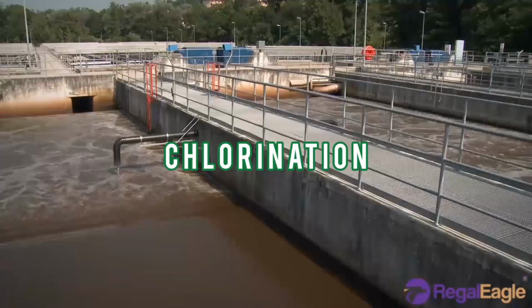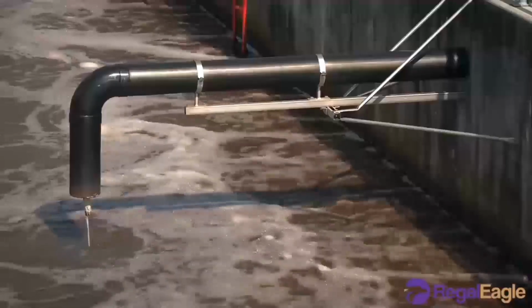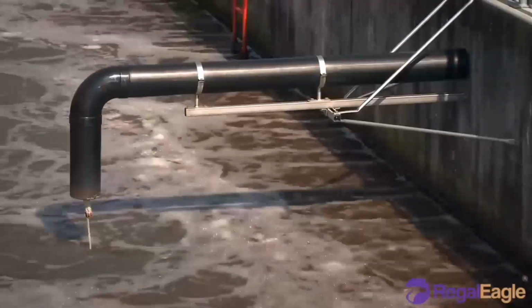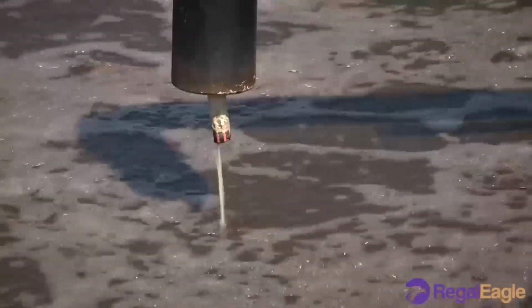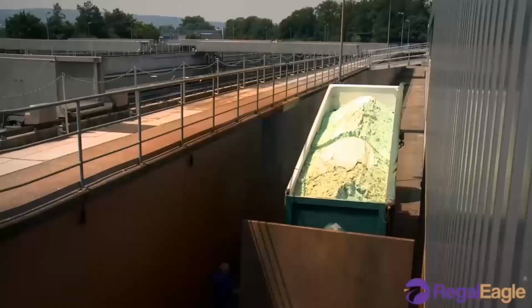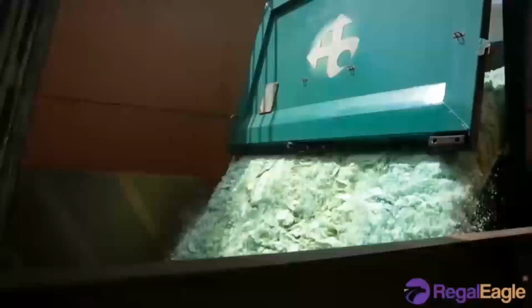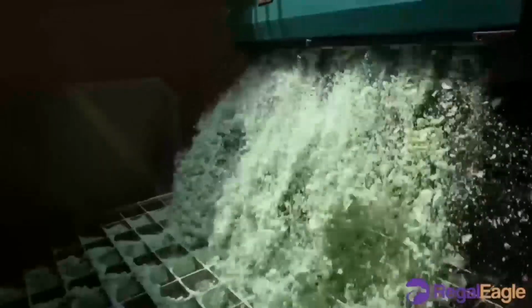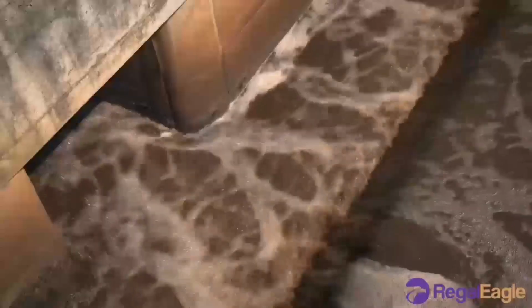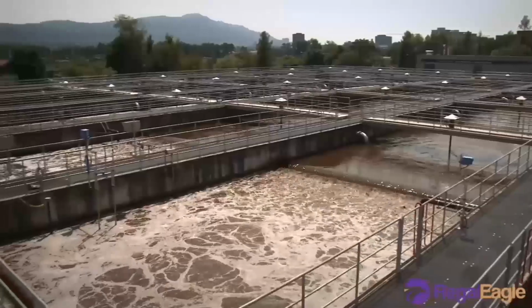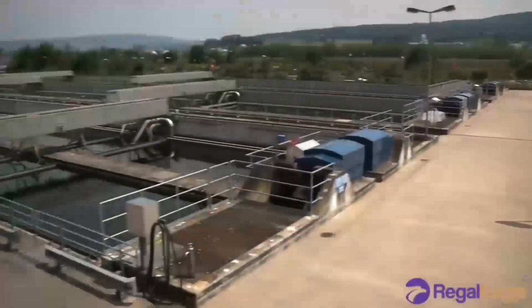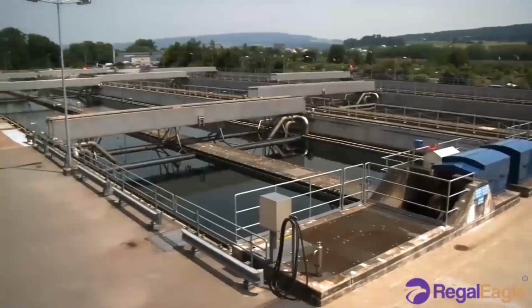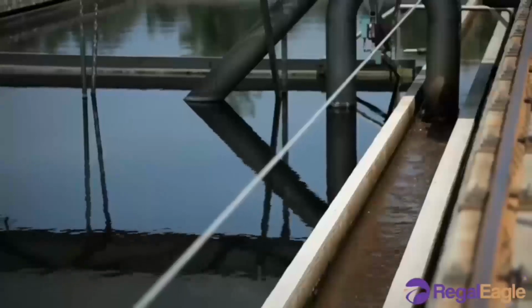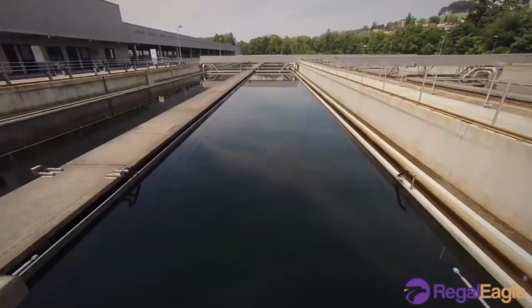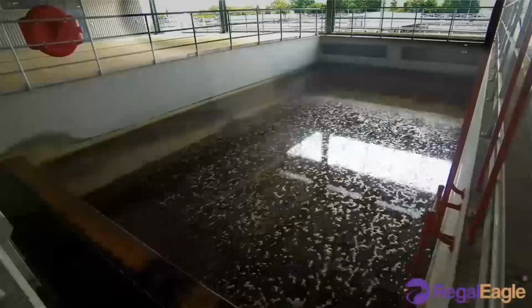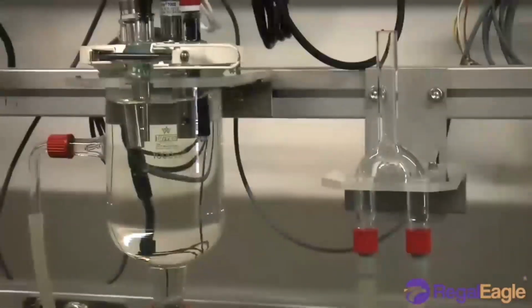Chlorination. After sedimentation, the water is disinfected to eliminate any remaining pathogenic microorganisms. The most commonly used disinfectant is chlorine. When chlorine is added to water, it reacts with any pollutants present, including microorganisms, over a given period of time referred to as the contact time. This chlorine stays in the water through the distribution system, protecting it from any microorganisms that might enter it until the water reaches the consumer.